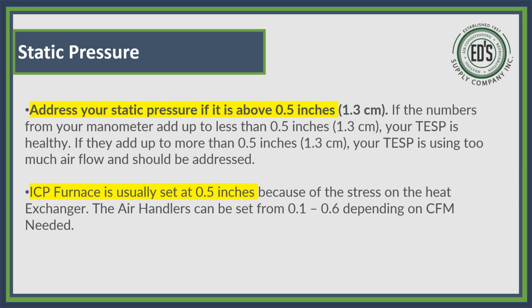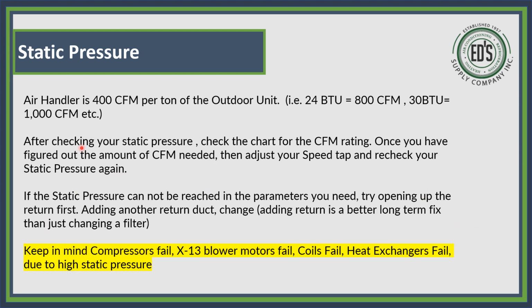There will be a static pressure chart that converts to CFMs. So let's look at it. An air handler is 400 CFM per ton of the outdoor unit. So if an outdoor unit is a 24, a 2-ton, that's 24,000 BTU. It's going to put out 800 CFM. So that's 2-ton, 800 CFM. A 30 is going to be 1,000 CFM.